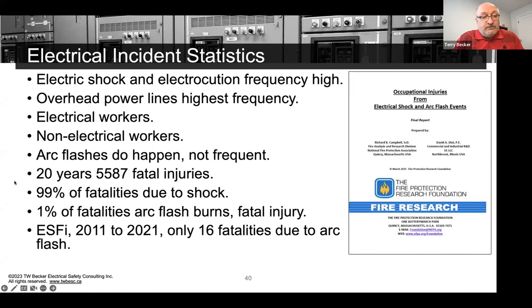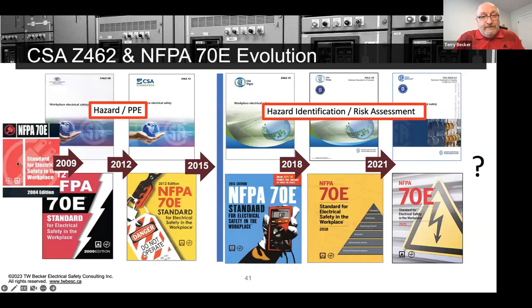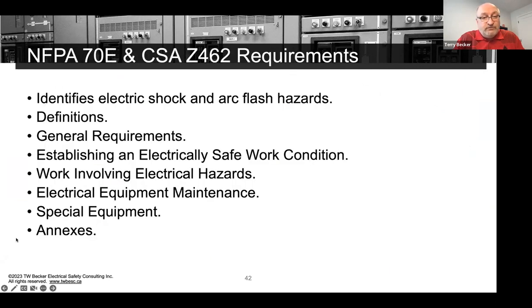It doesn't mean that arc flashes aren't occurring. They are, but they're resulting in burns and most likely curable burns. Whereas the electric shocks, we still don't have those reported. All we see is the electrocutions because those will be reported. The evolution of 70E and Z462 in the last 5 editions, initially just said get on PPE, in the 2008 or the 2009 and 2012, and they changed to hazard identification and risk assessment in the last 3 editions, and that will be sustained going forward.